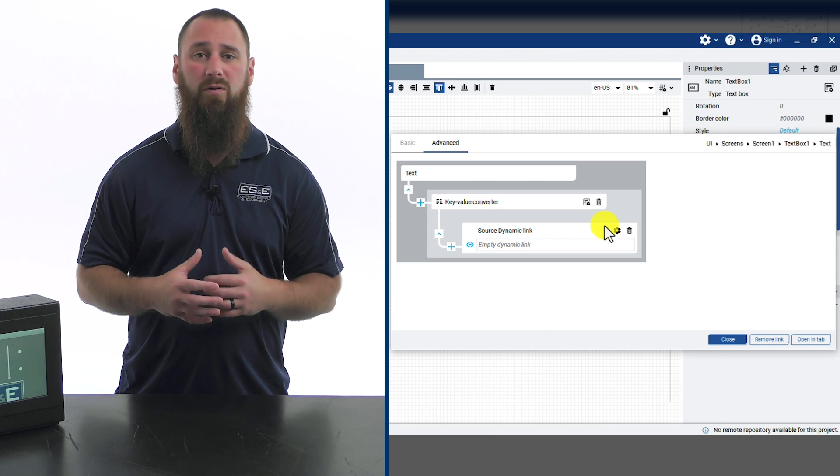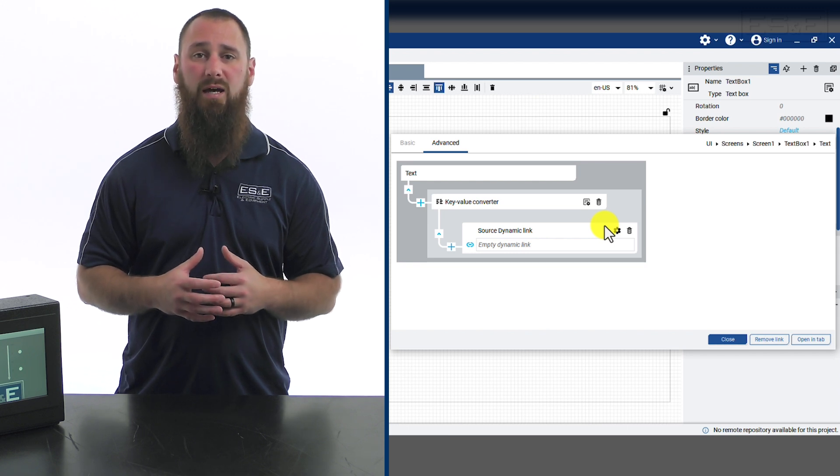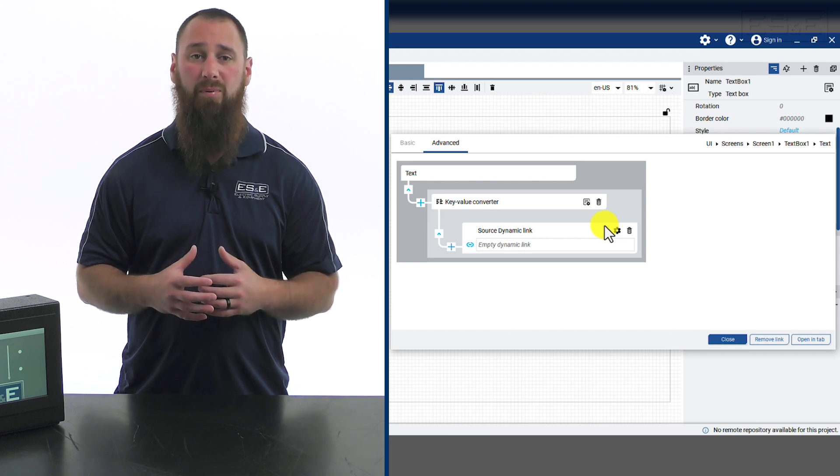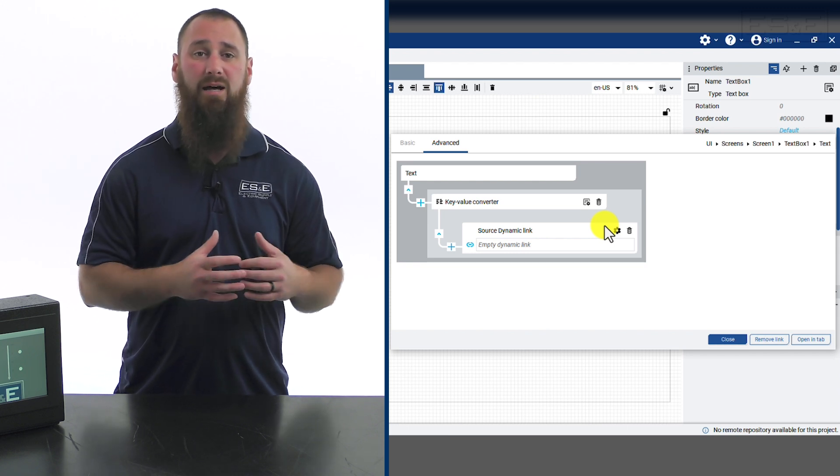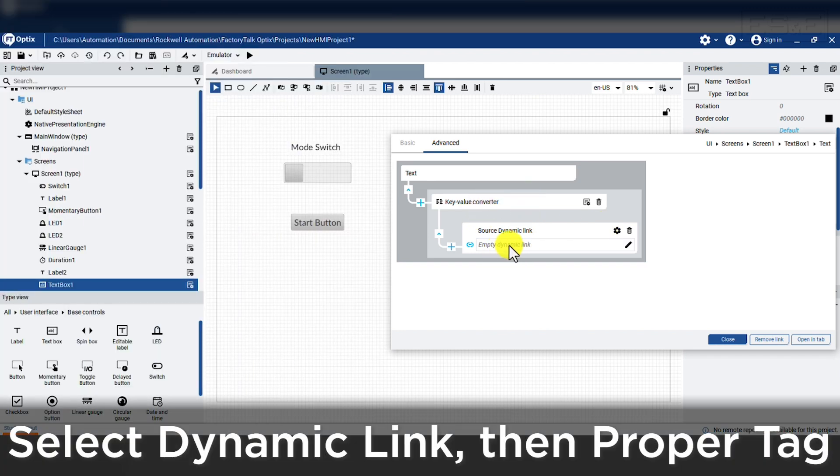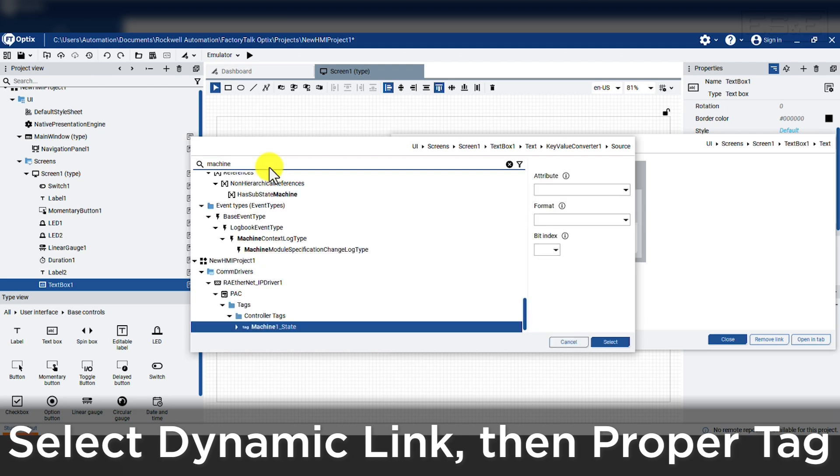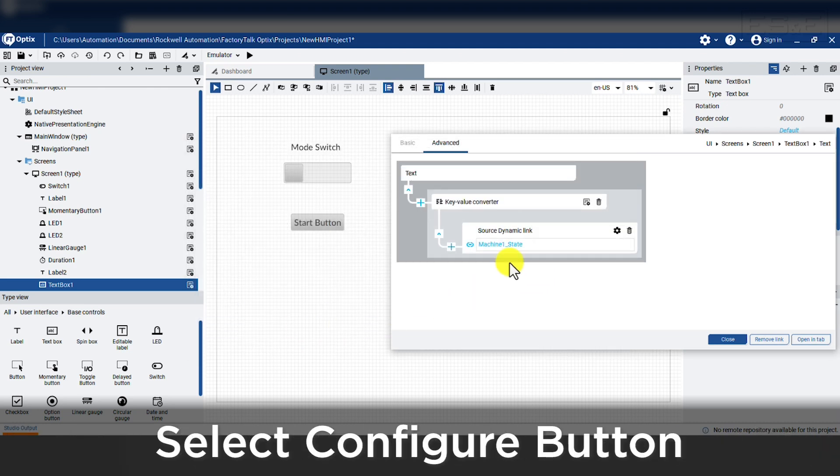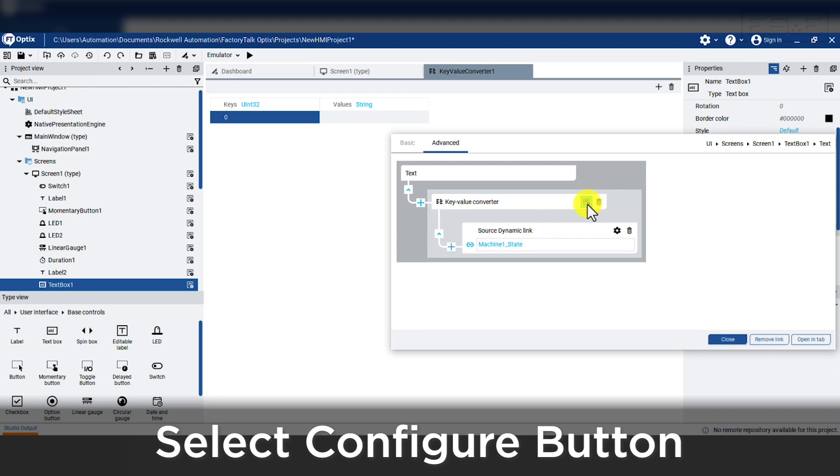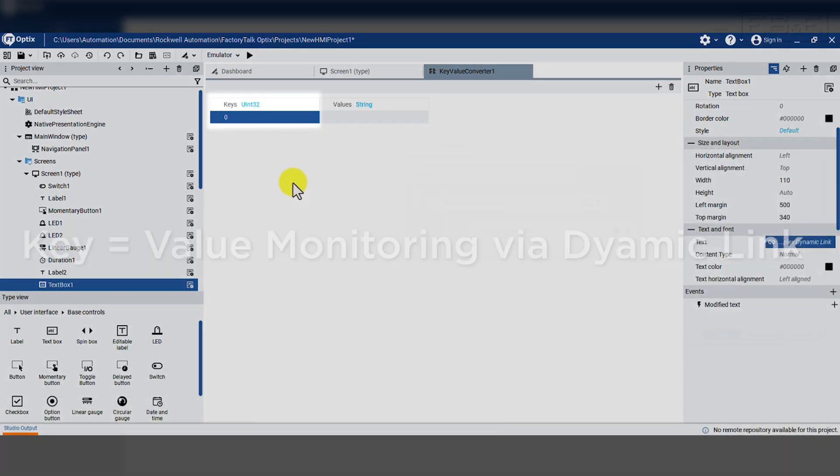Once we add key value, we will see the link box so we will find the tag called machine1 state. Then where the box says key value converter, we will select the configure button. This will open a new window where the key is the value we are monitoring with the dynamic link and the values are the property that we want to change. We will add two more states so we will have a 0, a 1, and a 2.